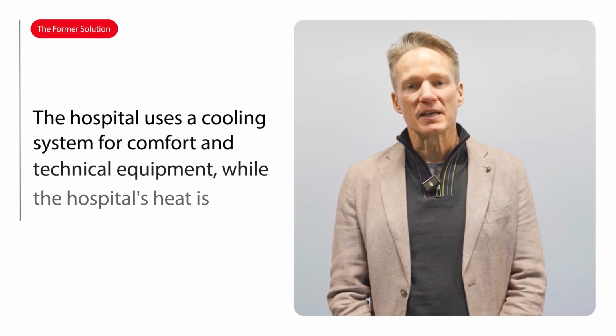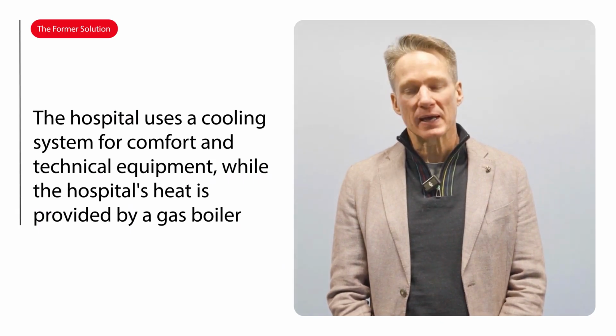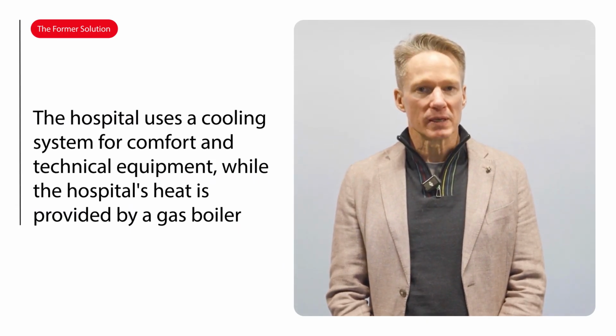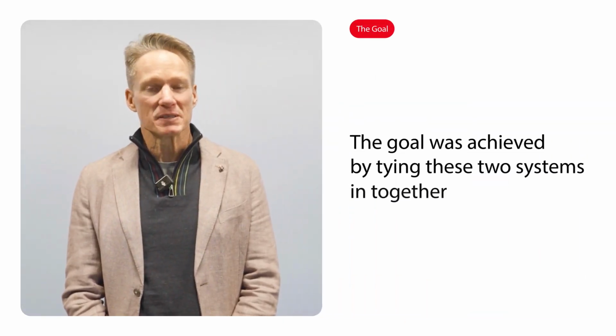Sygehus Sonderjylland, a hospital in the southern part of Denmark, wanted to become carbon neutral and to reduce its operating costs. So they started working with Danfoss and the local district energy utility to achieve these goals. Formerly, the hospital was getting its heating from gas boilers. They had both distributed technical equipment cooling for the MRI scanners and then also comfort cooling from a central chilled water system. The goal of decarbonization and reducing operating costs was achieved by tying these two systems in together.